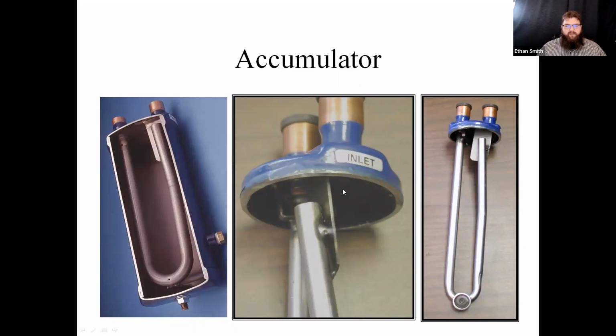The inlet side simply dumps into the top of the can. It's got a little splash guard here to keep it from going into the outlet of the accumulator, but it'll accumulate all that extra refrigerant in here as a liquid. It'll boil off into a gas and get sucked back into the compressor.